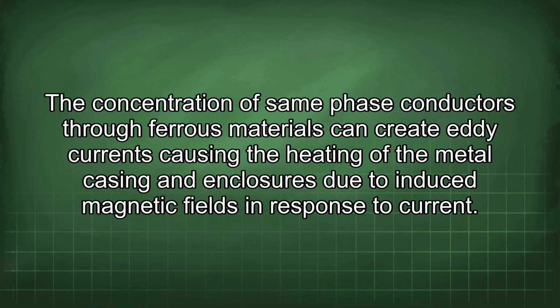The concentration of same-phase conductors through ferrous materials can create eddy currents, causing the heating of the metal casing and enclosures due to induced magnetic fields in response to current.